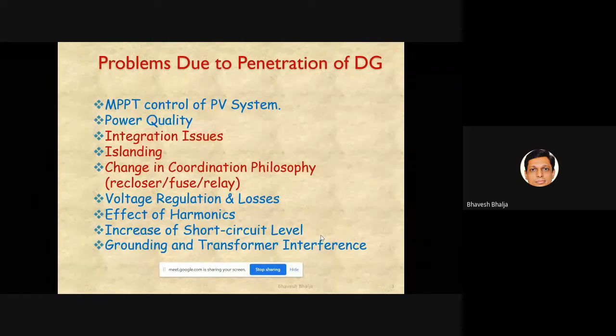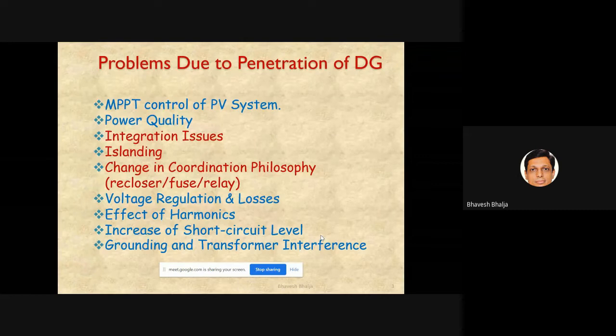The next issue is the change in coordination philosophy. We know that when we do not have any distributed generators, our distribution system, as you are well aware, has a primary distribution network and a secondary distribution network in our country. The primary distribution network works at 11 kV, and the secondary distribution network works at 415 volt three phase.